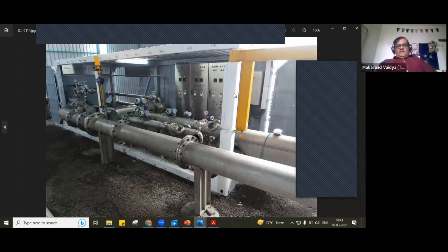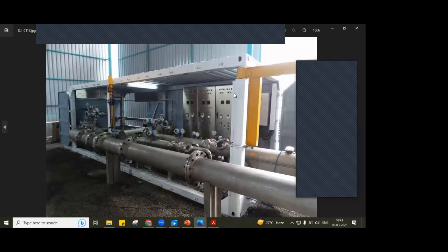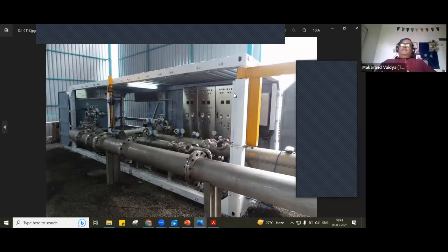I got it. Actually, during this setup, we had to take a rented DG set, DG van, and we conducted all the trials with all sorts of meters. Vortex, PD, Coriolis, and of course mass flow, everything was tested in front of us before it left for Jamnagar. And what is your standard meter where you are calibrating? It was first calibrated at that famous lab in Coimbatore. FCRI? FCRI. Okay, the first certificate I saw of FCRI. The pressure transmitter and temperature transmitter were from NTL. Those were simple, but the pressure transmitters are also quite required. And the flow computer and the cloud-based software were very innovative and very high-tech.